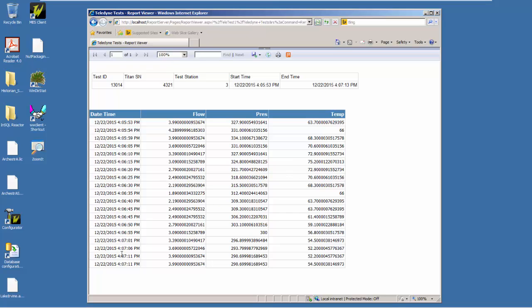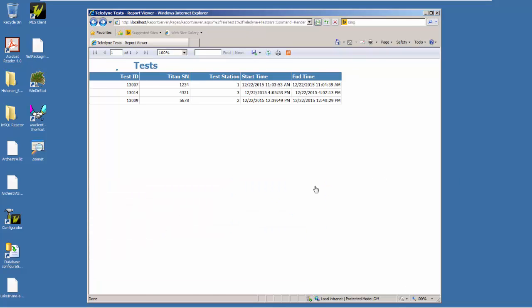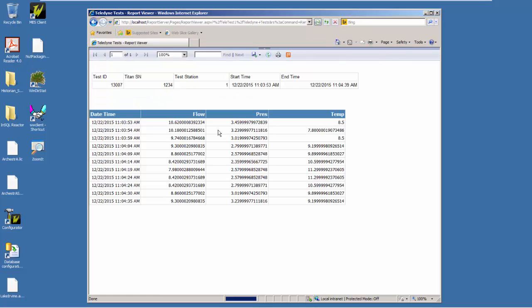So this is an example of the drill-down report — the ability to see all the information in my database for all my tests, and then drill down further to extract information from the Wonderware Historian. If I want to drill down into other tests, such as test station number one, I can view that report and all the process data that was collected during the time that test was run.